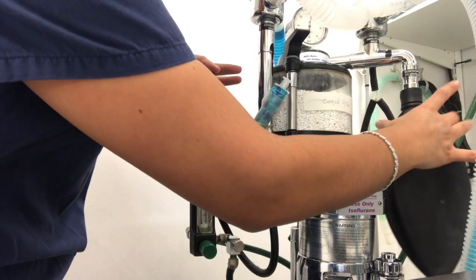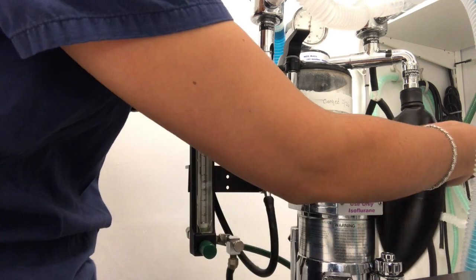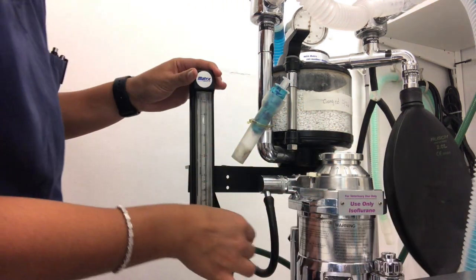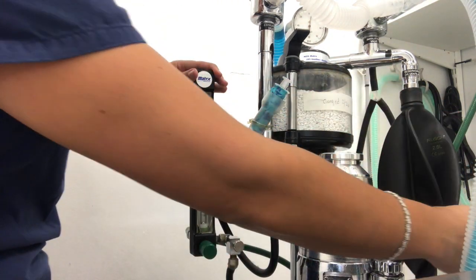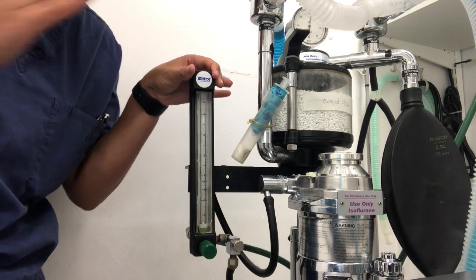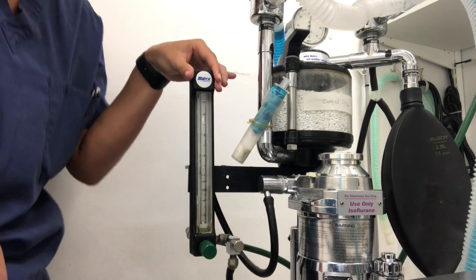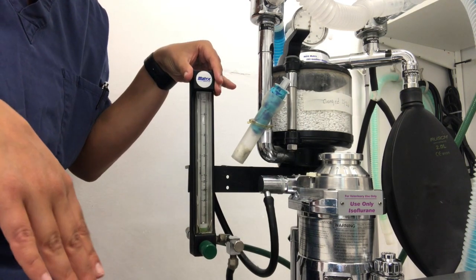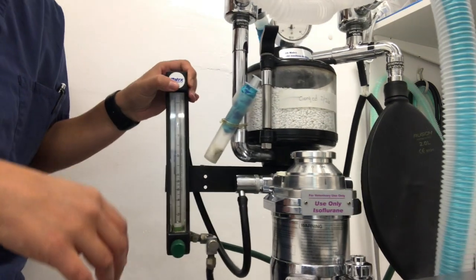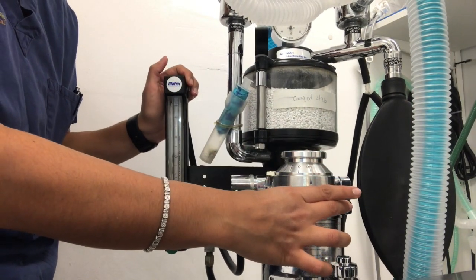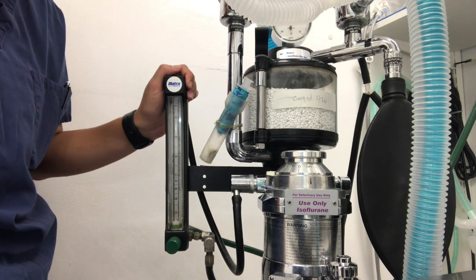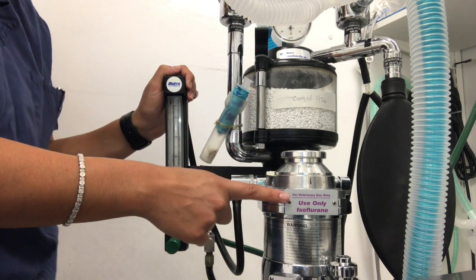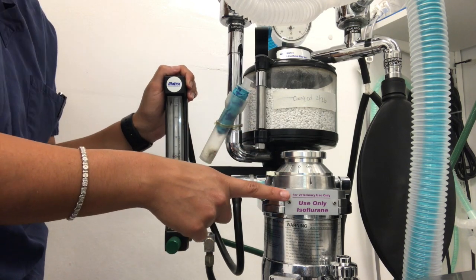And it's also good to dilute. It's also good to get rid of all the other anesthetic gas that is in the bag, so it will help us flush that out in case we want to increase the dose or in case we want to decrease the dose of gas that our patient is getting. All right, great. So next we have our anesthetic vaporizer. So this vaporizer actually converts our liquid isoflurane into a gas.